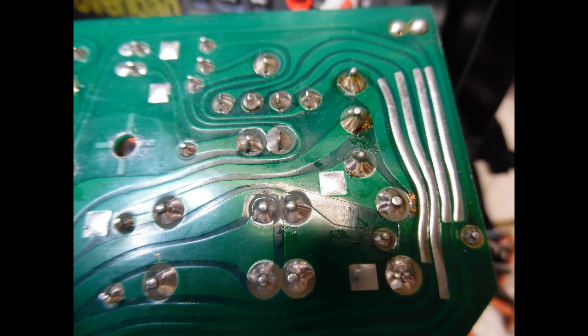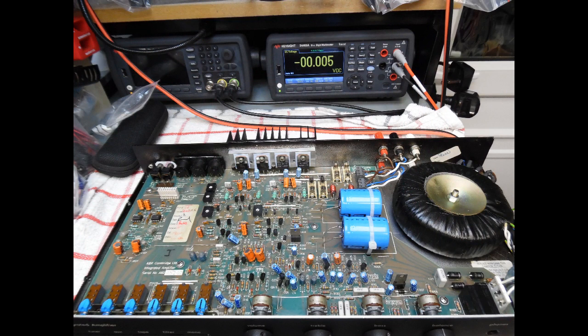When I put my meter on it, the reading was fluctuating, almost around 35 ohms or thereabouts, and unstable—floating around all over the place as you measure the resistance. So replace that fuse straight away, and then you know there will be no fluctuation on the power input stage for the amplifier.